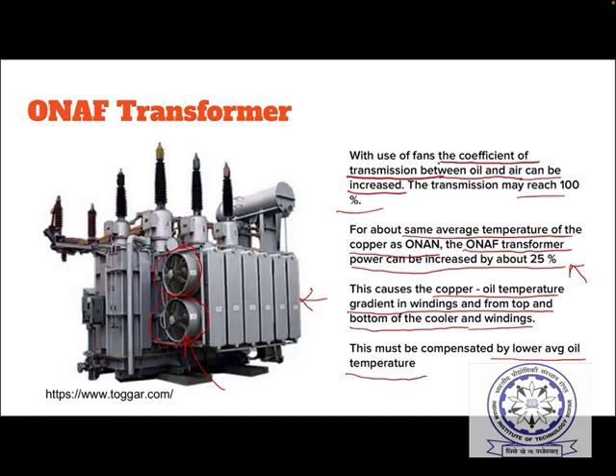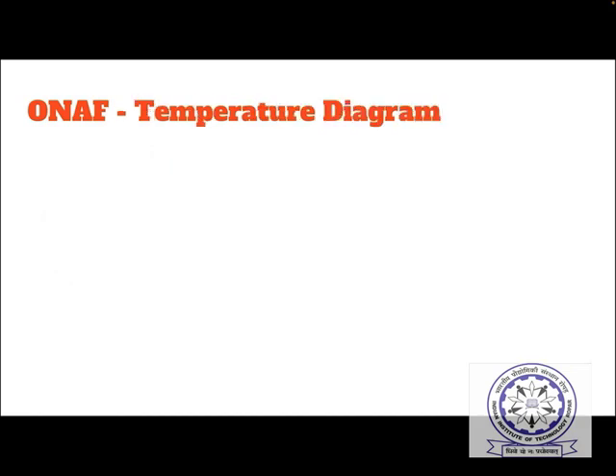So this must be compensated by a lower average oil temperature because the gradient increases. Therefore the oil average temperature should be smaller, because we cannot increase the temperature of the copper. So if the gradient is more, the oil temperature has to be low. And let us see the ONAF temperature diagram. So this is like this actually. Since the copper portion has to be maintained more or less the same as the previous case.